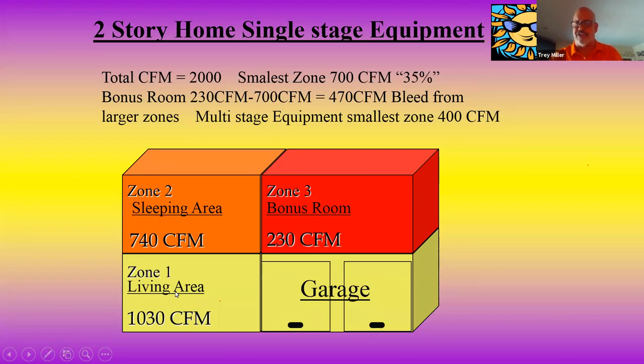Guys, it's not going to overcondition the area, but you have given them a house that's so much more comfortable than anything they had before. And to tell you the truth, with a thermostat down here in the living area, the bonus room is pretty much inoperable. It's too hot, unless they're going to put a window unit or a mini split or something like that in there, which a lot of guys do. And let me tell you something, guys, mini splits, they're called ductless split systems. It's where you can't get duct. Guys, for the cost of the condenser and the disconnects, I can zone the whole house, not just one room.